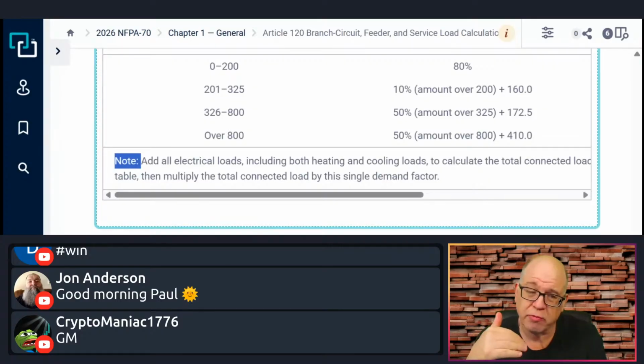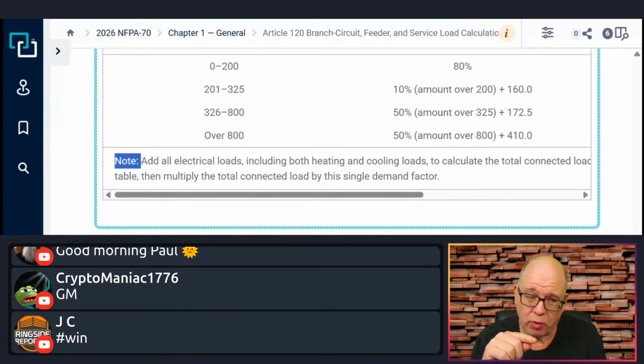Any note that's below a table, just like with ranges in 220.55 or 120.55 in the 2026 edition, those notes are very much part of the table. So you have to meet them, you have to utilize them. Whereas an informational note is just really good information - you can't use that to win any argument with an inspector. But at the end of the day, informational notes to me are just good roadmaps to send you to certain places in the code that you need to be. But these notes are very much applicable.